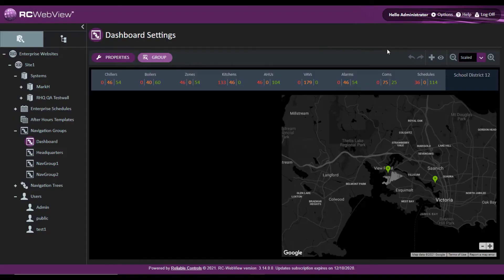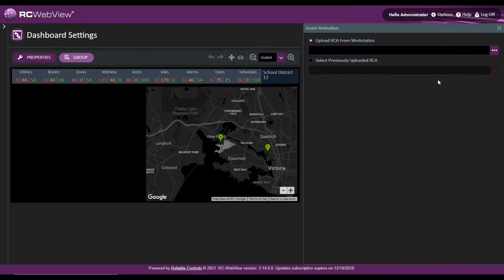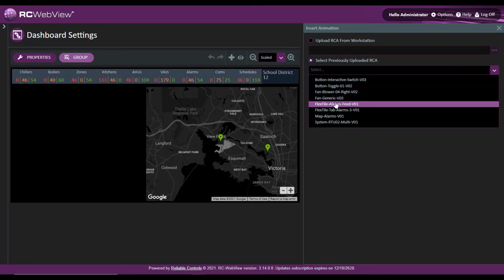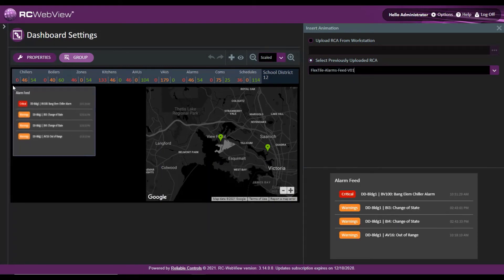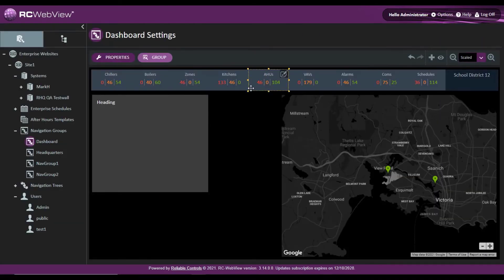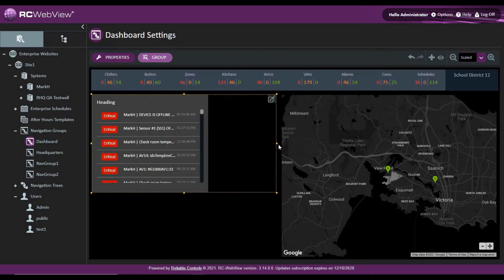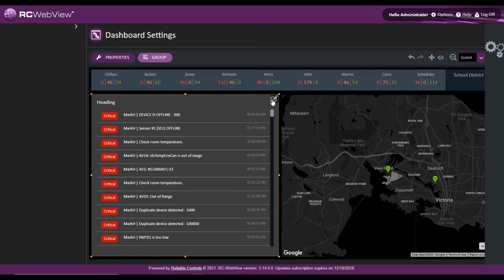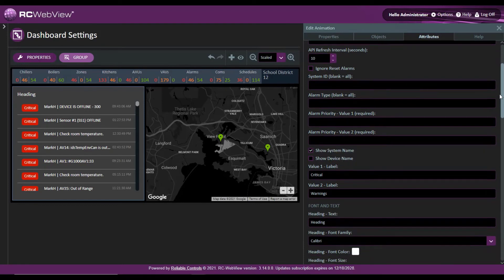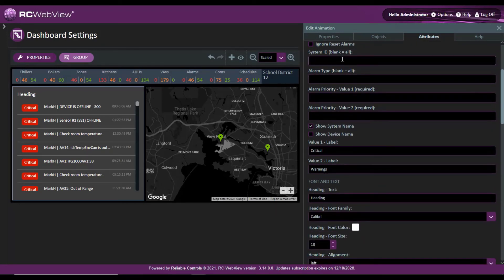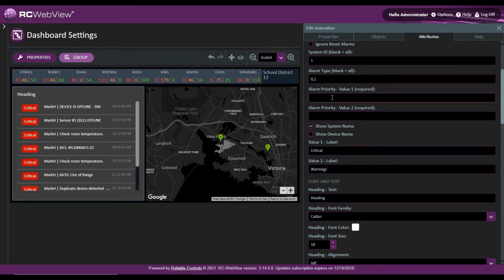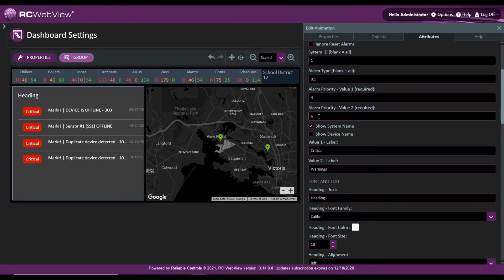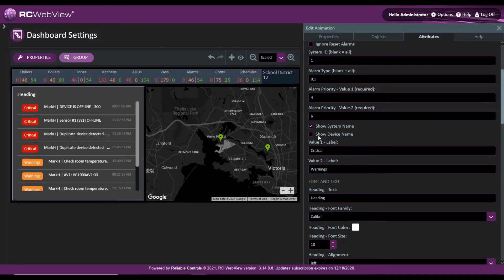To use an alarm enabled animation, I can click here, click animation, and go to my previously uploaded Reliable Controls animation and grab this flex tile alarms feed. I'll drag this into the canvas and size it using the bars. Then I'll change settings with the attributes tab — I'll grab the alarms just from system number one, choose alarm types zero and one, and alarm priorities four and six. I can also change the system name or device name. Notice how on the left hand side it's updating in real time.